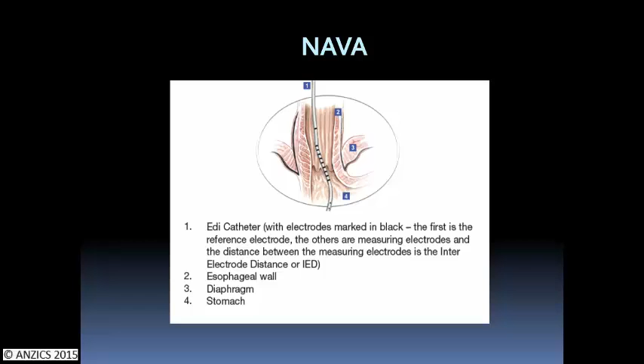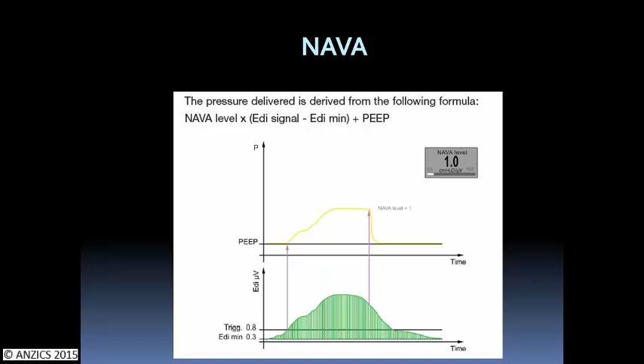And as you can see there, that's the electrical signal at the bottom, so it cycles on when it first detects it, gives you the amount of support related to the height of the signal, and then it cycles off when the signal drops to a certain percentage of what the peak signal was.